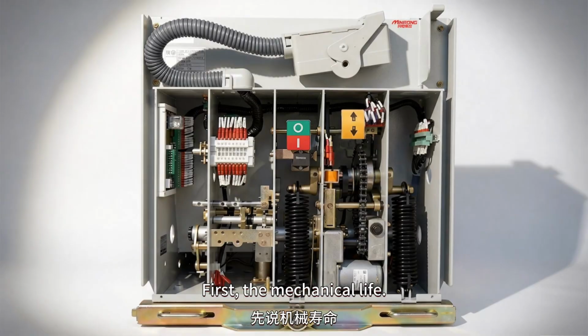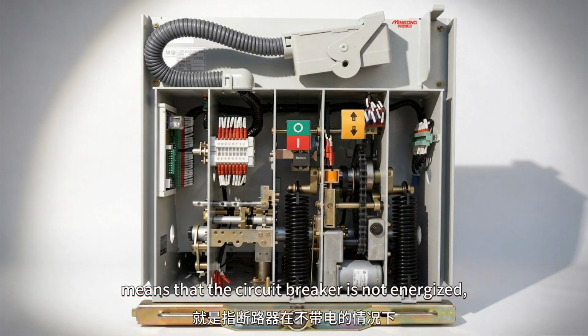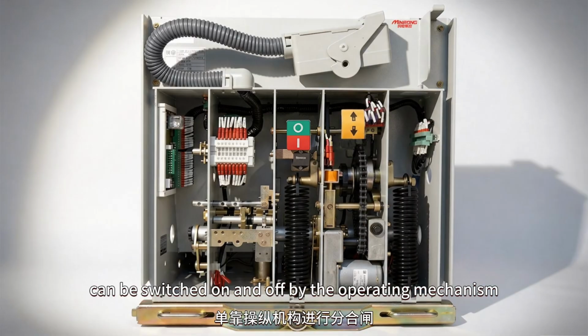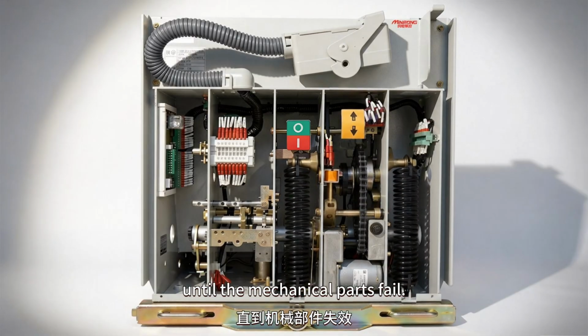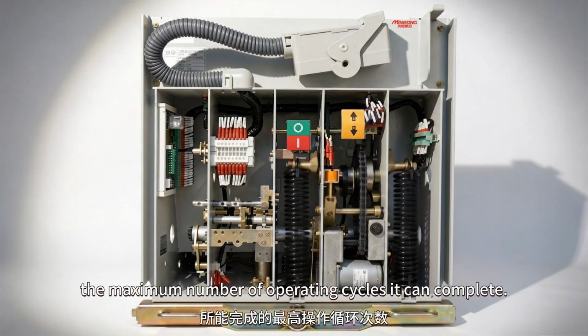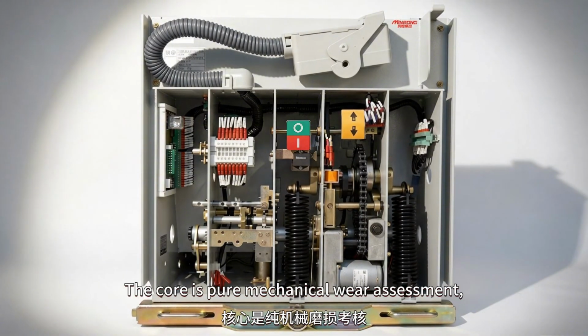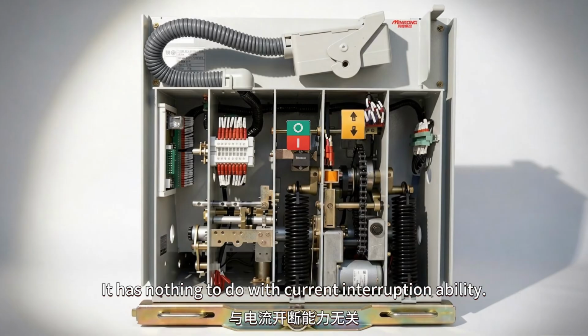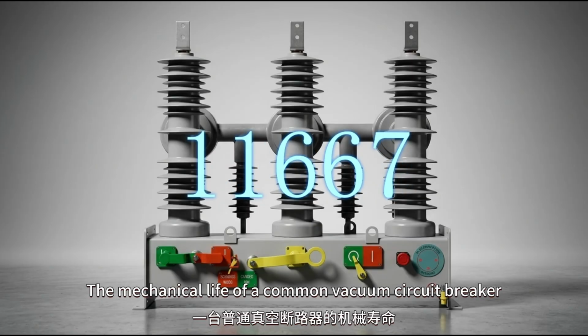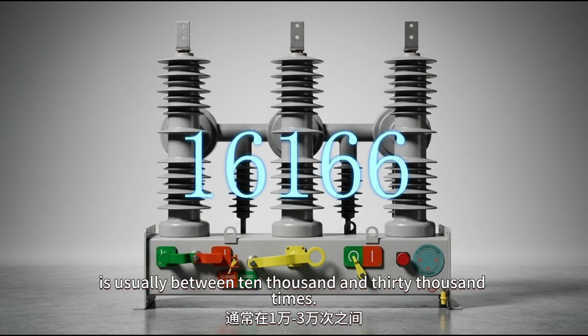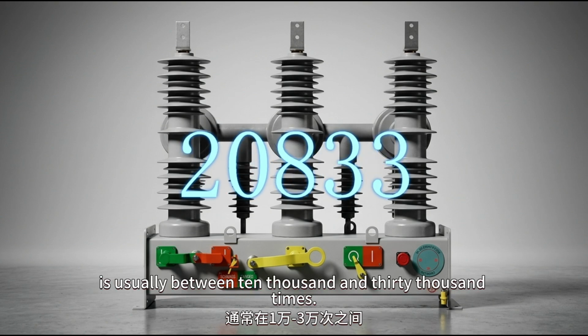First, the mechanical life means that when the circuit breaker is not energized, it can be switched on and off by the operating mechanism, up to the maximum number of operating cycles it can complete until the mechanical parts fail. The core is pure mechanical wear assessment. It has nothing to do with current interruption ability. The mechanical life of a common vacuum circuit breaker is usually between 10,000 and 30,000 times.